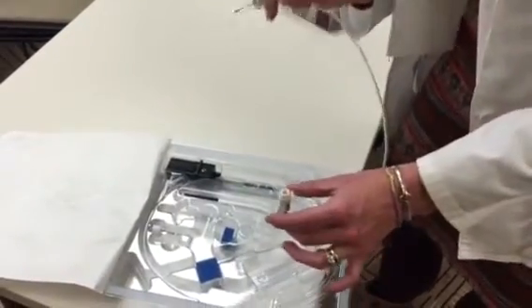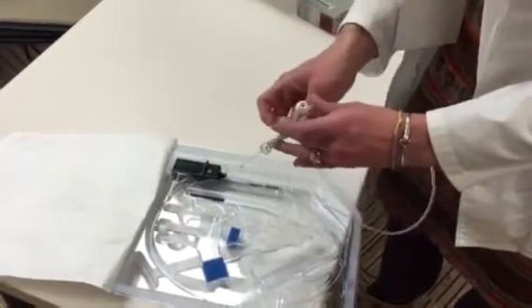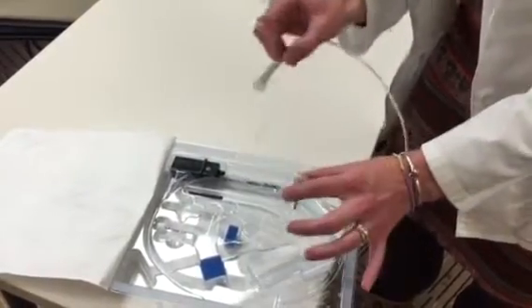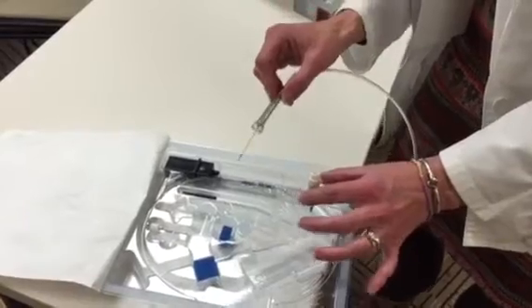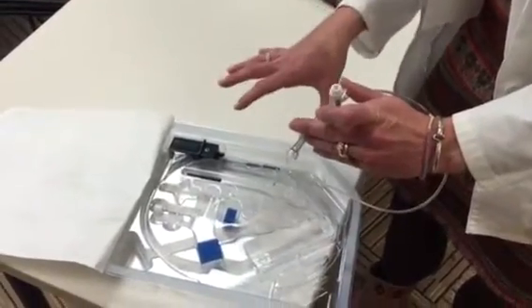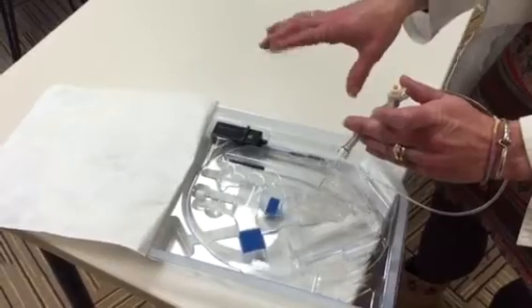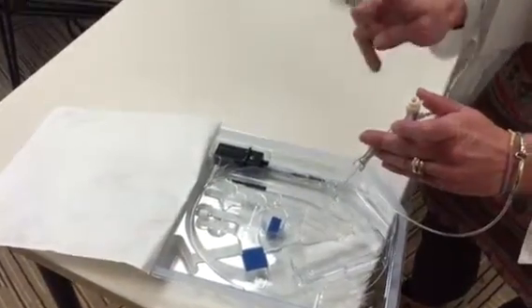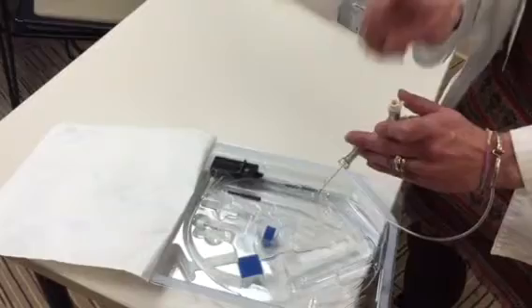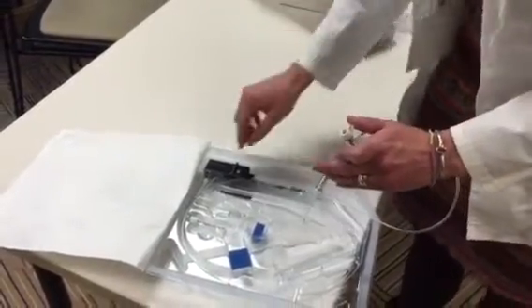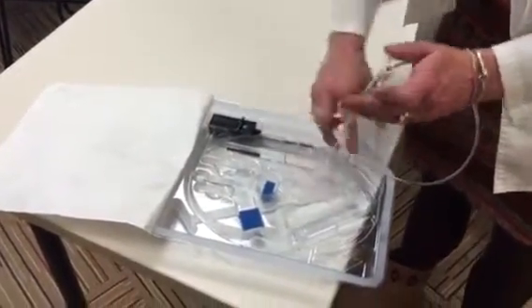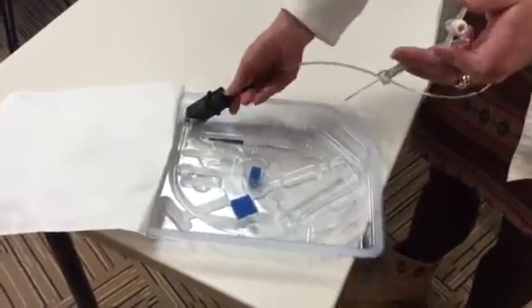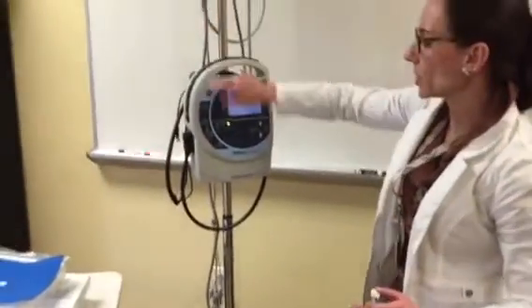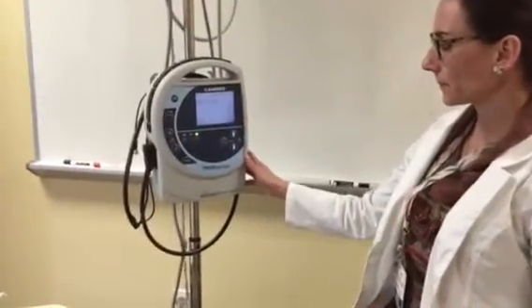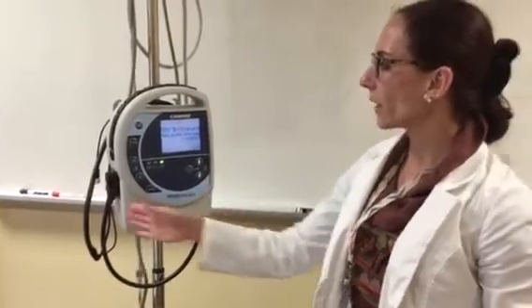There is one very, very important piece that needs to be done before inserting the ICP catheter into the bolt, and that is zeroing. Remember, with this particular setup, the Camino with fiber optics, these things get zeroed just one time ever. They will be zeroed once prior to insertion and then never again. Tuck that away. So in order to zero it, it has to be hooked up to the Camino. So this piece here, we'll bring this over to the Camino. You'll want to turn it on by pushing the start-stop button. Let it do its little self-check.